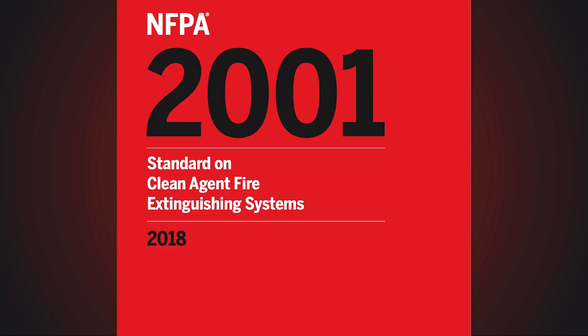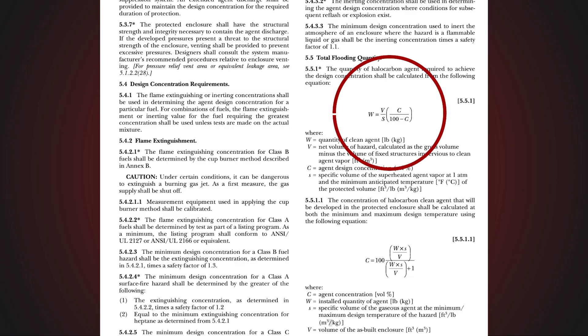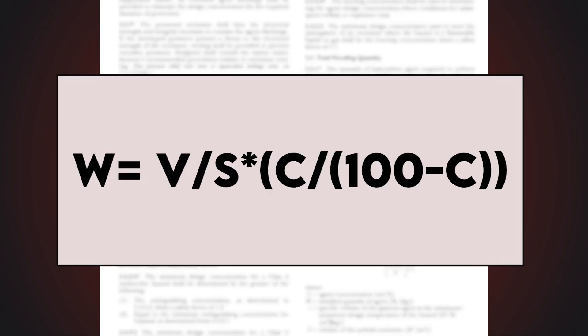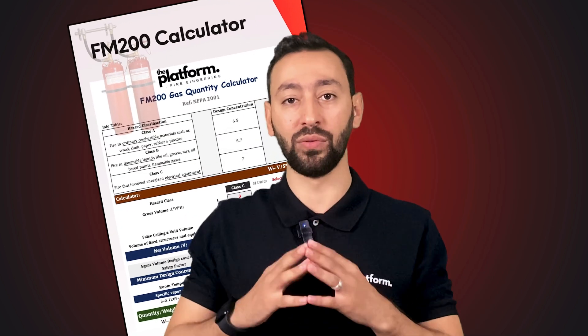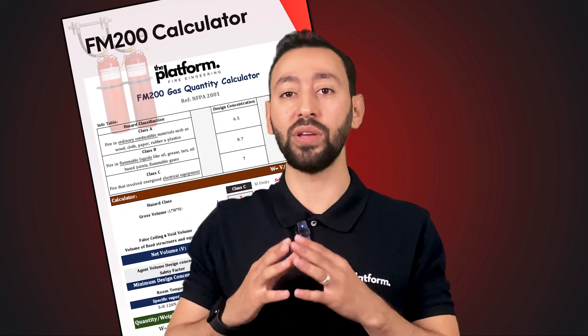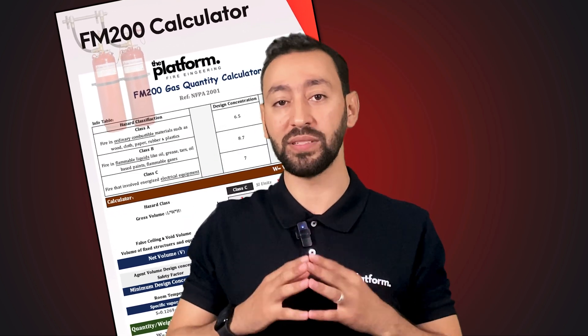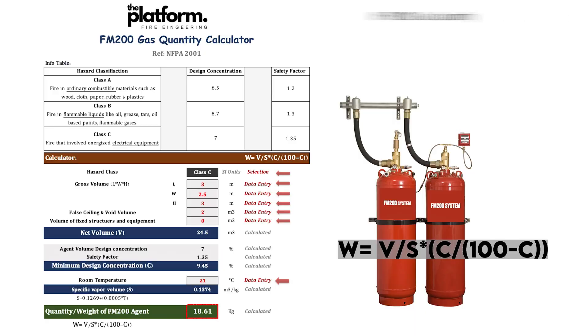Referring to NFPA 2001 standard, the required quantity of FM 200 gas is calculated using an equation which my calculator is designed based on. This equation includes variables that can be calculated as follows.